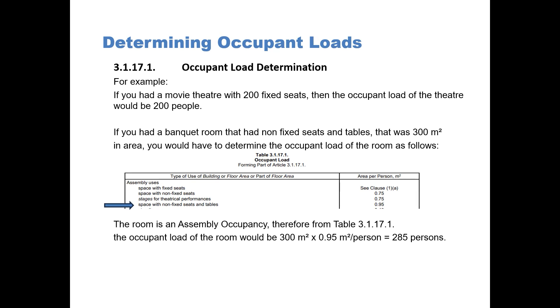If you had a banquet room that had non-fixed seats and tables that was 300 metres squared in area, you would have to determine the occupant load of the room as follows. You would first go to Table 3.1.17.1 and look up assembly, because a banquet room is an assembly occupancy. You look up space with non-fixed seats and tables, and you get a value of 0.95 metres squared per person. You would then calculate the occupant load using the room area of 300 metres squared divided by 0.95 metres squared per person.